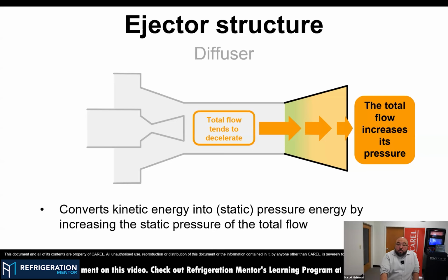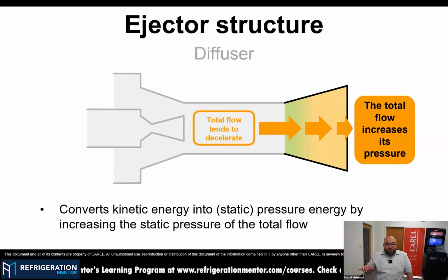Yeah. And also as a positive effect, Trevor, we know that CO2 transcritical sometimes could be a little bit challenging, because during summer you need an extra capacity for the compressors, and during winter you have too many compressors, so it's always hard to regulate the rack at subcritical conditions. Using the ejector, you might be able to reduce the amount of compressors, or at least reduce the sizing of your compressor, since you would need less compressor during summer, and this would make your system more stable, because when you have a smaller compressor, you have more flexibility in terms of modulation. So you can reach that specific point to maintain the system running and the compressor on most of the time.